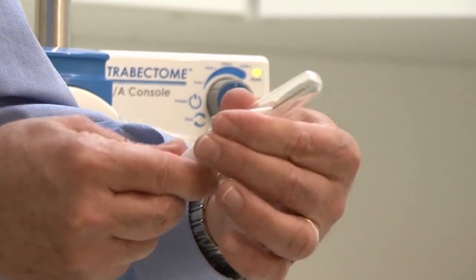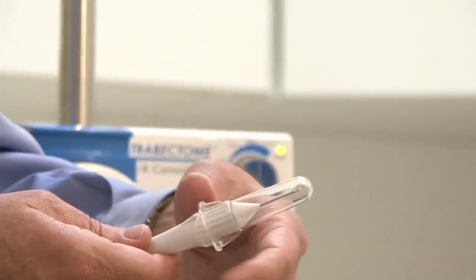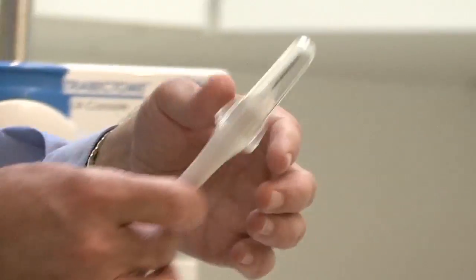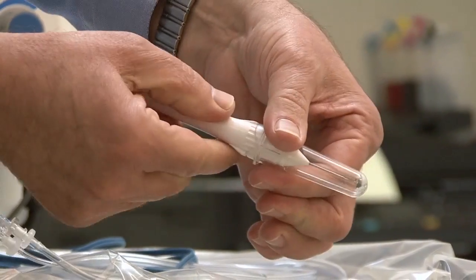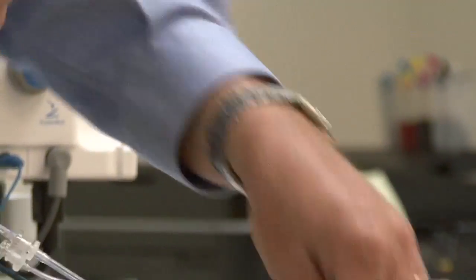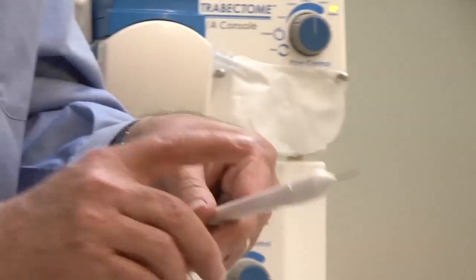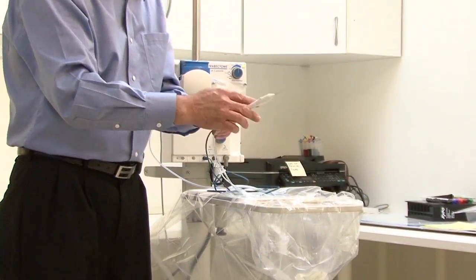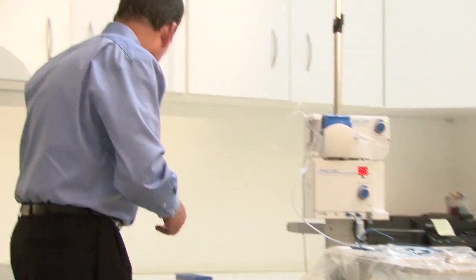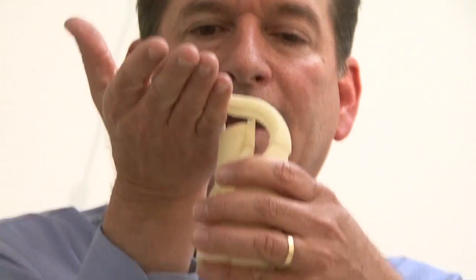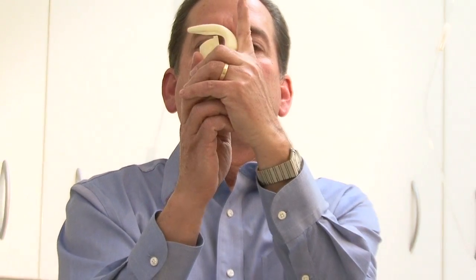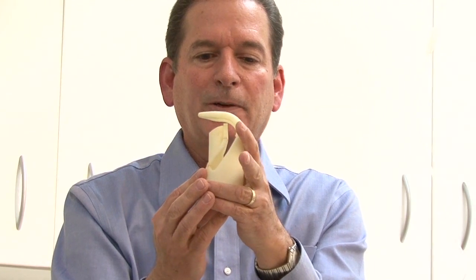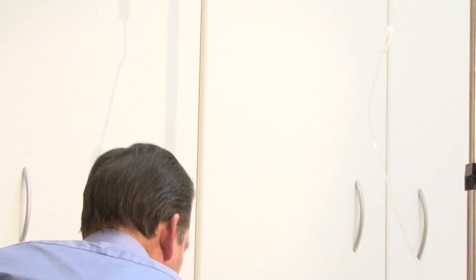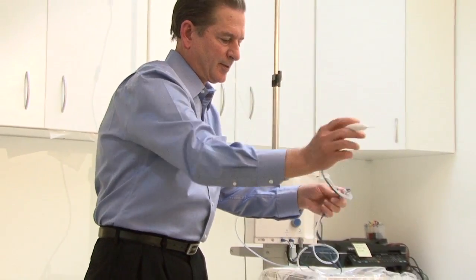So we really want to avoid pushing the cap off to the side or scraping the cap along the plastic or touching the tip to anything. What we want to do is just twist to open, carefully remove it without touching anything, and hand it on and off of the surgical field again without the tip really touching anything. You can imagine if the tip snags a drape, what happens is, if we go back to our model, this delicate little tip will snag and it'll actually bend the tip, and then we have to replace the handpiece because it's no longer functional. So if we're careful in how we handle the handpiece, that's really no problem at all. We just want to be careful not to snag the tip on anything.